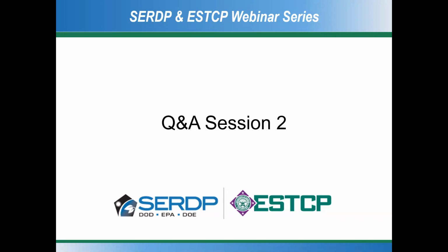Thank you, Gwendolyn. This next question is from McCool Controls and Engineering. In a scenario where one terminal VAV, or variable air volume, zone is modulated to a minimum flow equal to the required ventilation rate, doesn't the whole air handling unit then have to be on 100% outside air? Does this possibly result in higher energy costs overall?